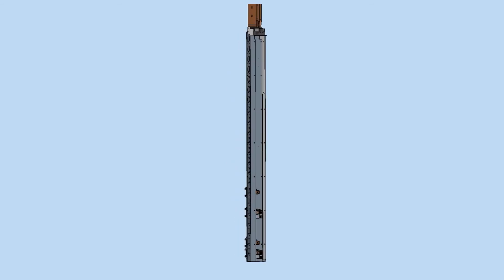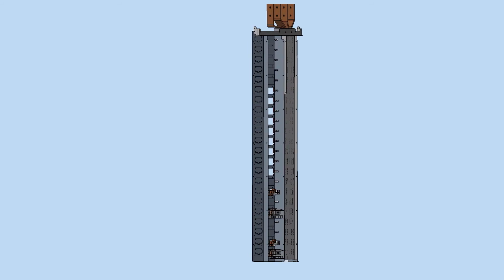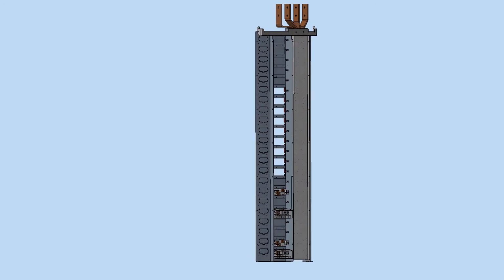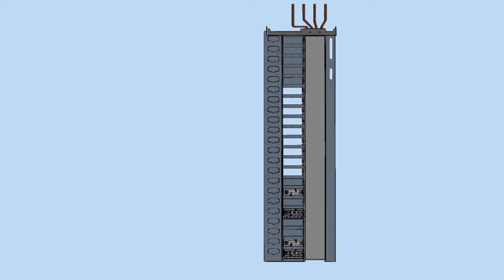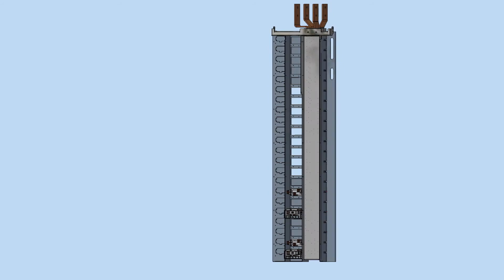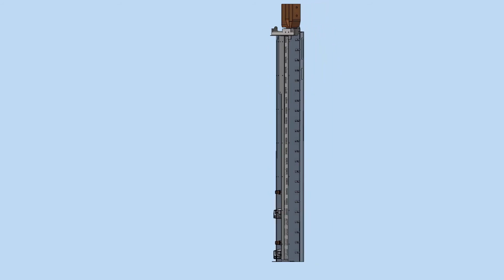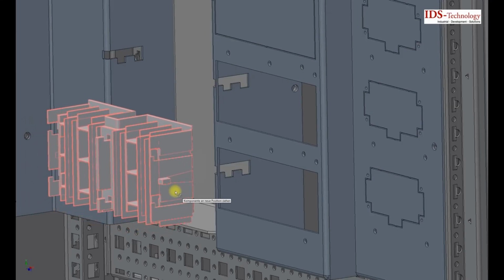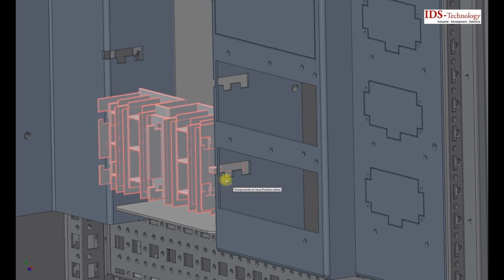Wherever the EST wall will be installed, it is dividing the switchboard in drawer compartment and cable compartment. Furthermore, the EST wall is prefabricated in steps of 75 mm, alternative 100 mm. This makes changes and modifications easy to realize. The components belonging to the EST wall can be mounted easily without tools or screwing.